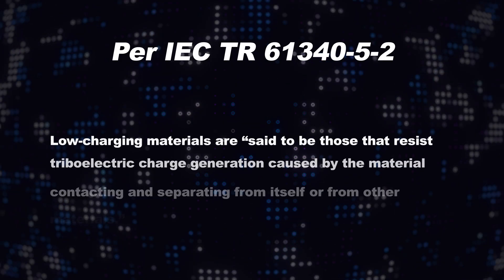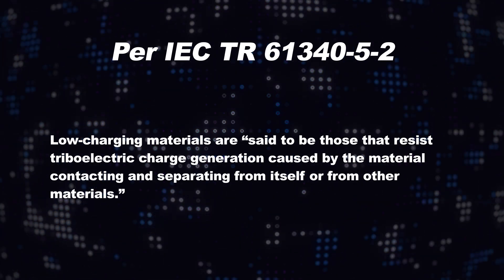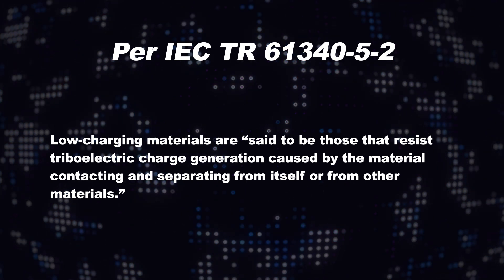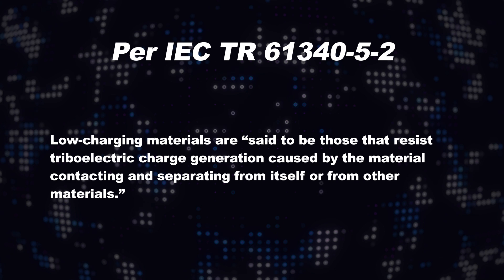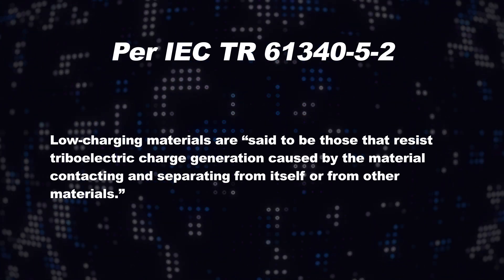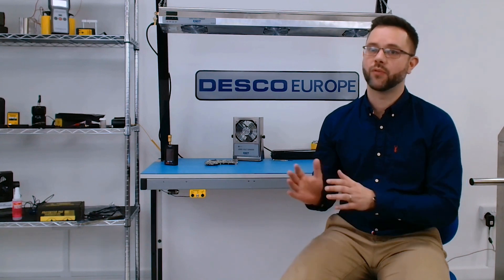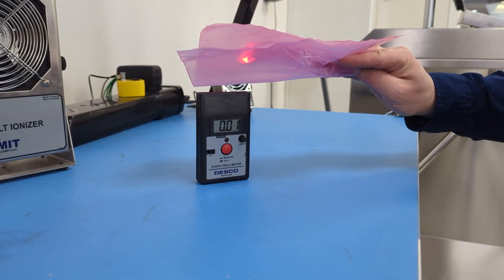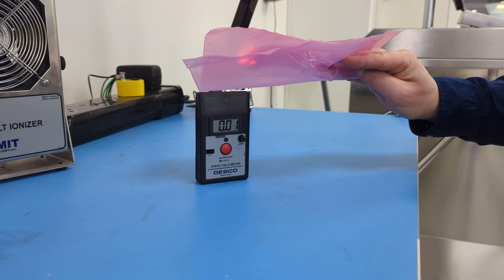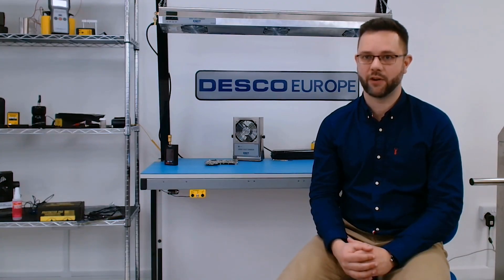Low charging materials, according to IEC TR 61340-5-2, are said to be those that resist triboelectric charge generation caused by the material contacting and separating from itself or other materials. So while materials of this nature will not necessarily assist in providing a pathway to ground for an electrostatic charge, they will also not be causing a problem by introducing a static charge into your EPA. These types of materials are therefore fine to have in the electrostatic protected area.